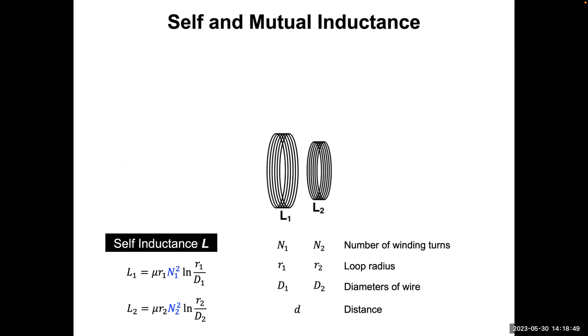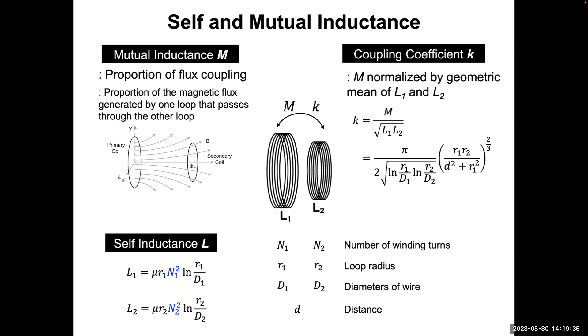This is a metric between 0 and 1, and it says how tightly the two coils are coupled. 0 means no coupling, 1 means perfect coupling. For implantable devices, 0.1 or 0.2 is just a rough or typical number for the coupling. When tightly coupled, it can go up to 0.5. If loosely coupled, it can go below 0.1.